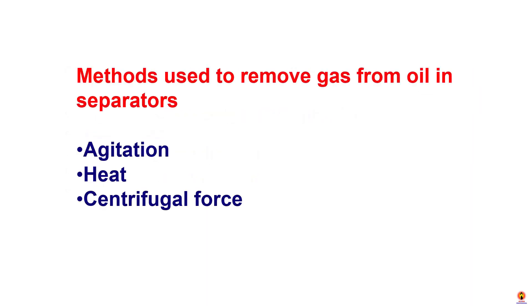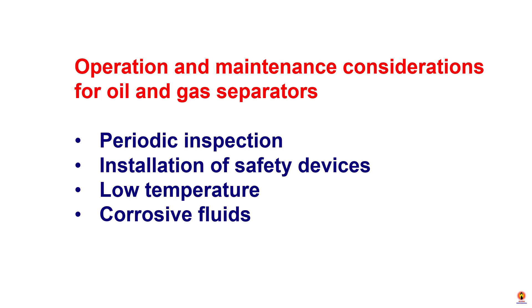Methods used to remove gas from oil in separators: agitation, heat, and centrifugal force. Operation and maintenance considerations for oil and gas separators include: periodic inspection, installation of safety devices, low temperature concerns, and corrosive fluids.